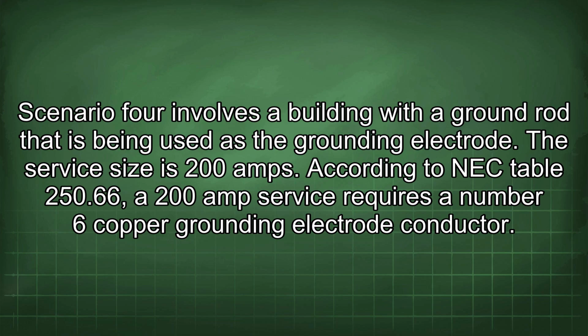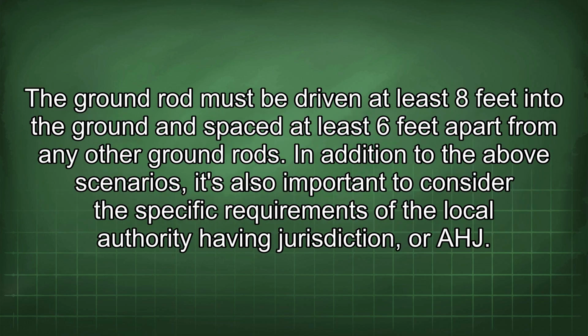Scenario 4 involves a building with a ground rod that is being used as the grounding electrode. The service size is 200 amps. According to NEC Table 250.66, a 200 amp service requires a number 6 copper grounding electrode conductor. The ground rod must be driven at least 8 feet into the ground and spaced at least 6 feet apart from any other ground rods.